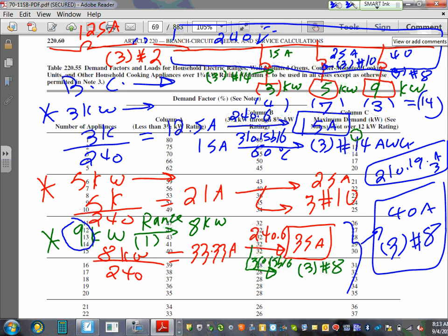Any comments, guys? Any questions? So we size the feeder. By the way, it could also be a service to the building. Same thing, feeder or service, same size. These are branch circuits. See how we size it based on the actual load. Except if it's a range, you're allowed to use the code. And at the bottom line, you shall not go less than 40 if your range was 8 3/4 and larger. Any comments, guys? Any questions about that?